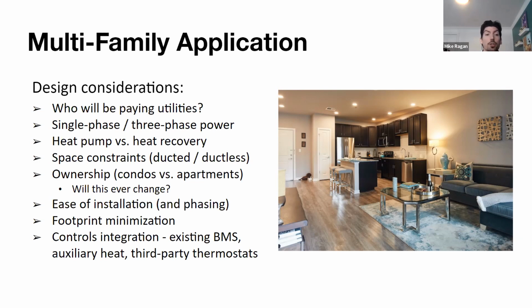And here's an important one that oftentimes gets overlooked: ownership. Are these condos, with owners of the condos? Are these apartments where people are just renting? Are these apartments now, but one day they may be condos? That's important to know, because when changing ownership of an HVAC system, if you own a condo with just one fan coil attached to a centralized condensing unit that serves the whole building, any changes to that HVAC system are officially going to require buy-in from everyone in the condo association. But if you're a condo owner and you have a split system, one outdoor unit that's yours and one indoor unit that's yours, you can make those adjustments pretty seamlessly. So that's definitely a consideration to take into account.